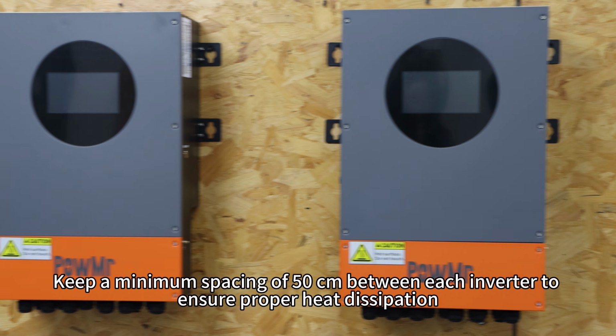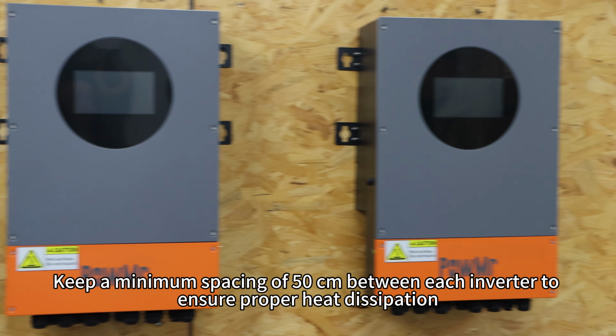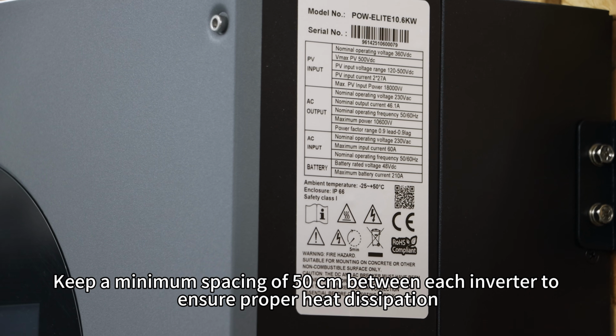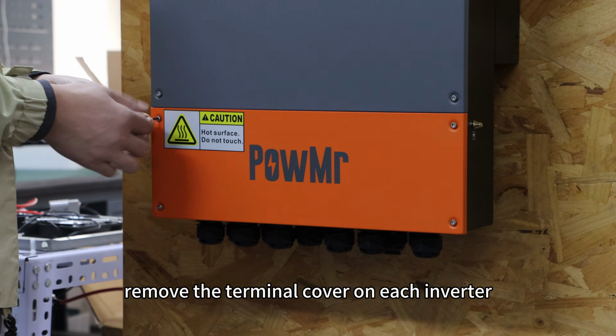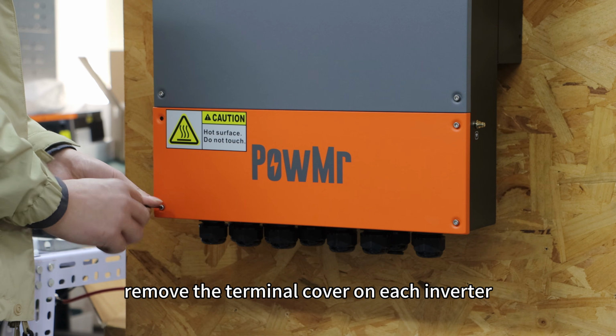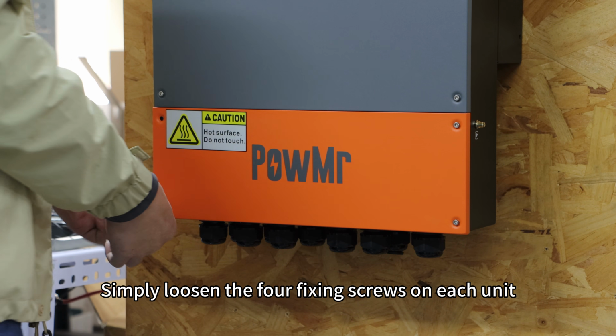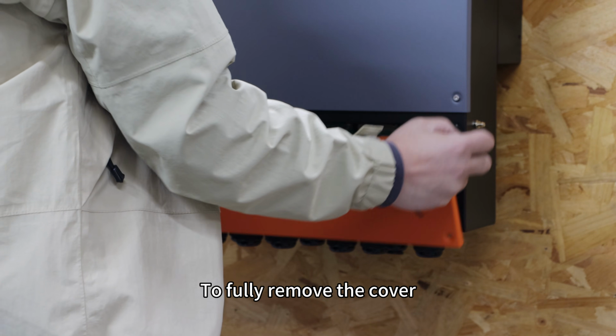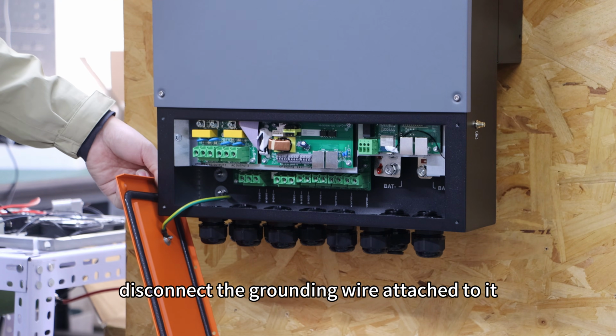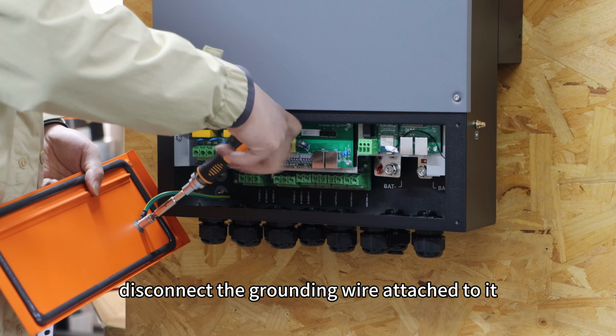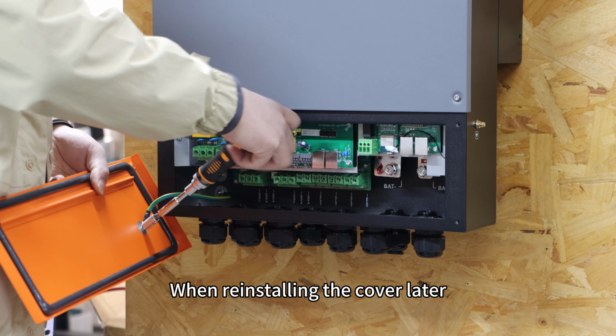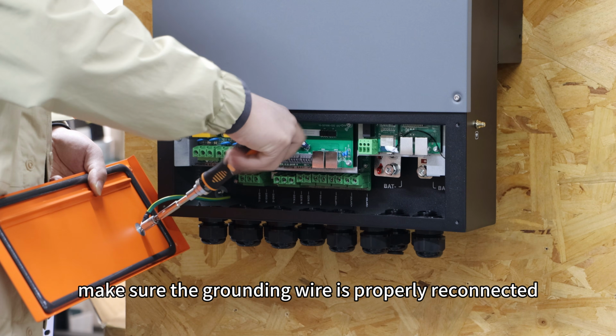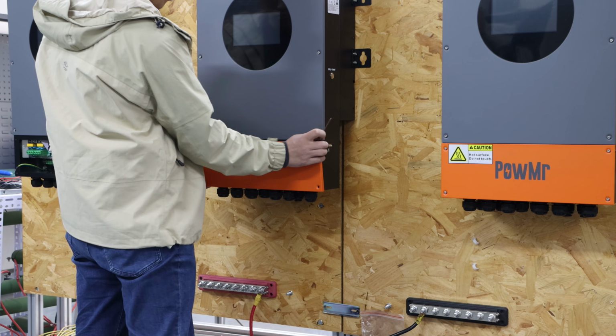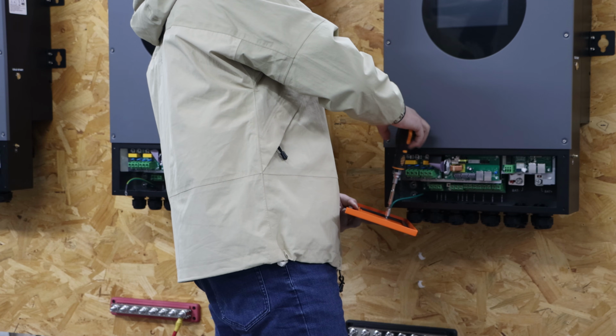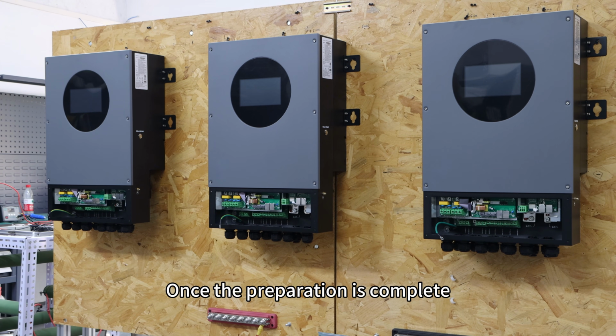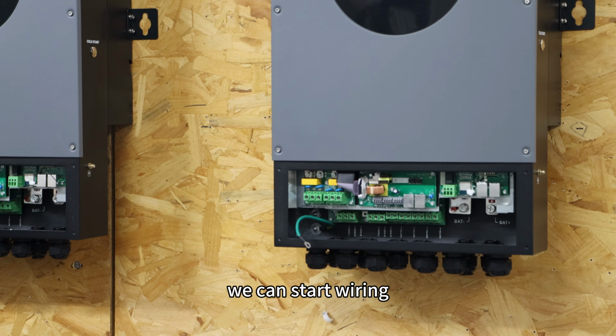Keep a minimum spacing of 50 cm between each inverter to ensure proper heat dissipation. Next, remove the terminal cover on each inverter. Simply loosen the four fixing screws on each unit. To fully remove the cover, disconnect the grounding wire attached to it. When installing the cover later, make sure the grounding wire is properly reconnected. Once the preparation is complete, we can start wiring.